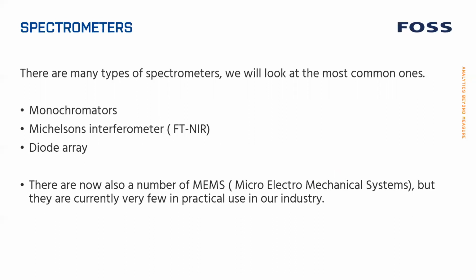How deep will NIR light penetrate into the sample in reflectance mode? Suppose sample are well grind. Well, if you do reflectance, in the shorter wavelength range, it will penetrate maybe 1 to 2 millimeters. When you go higher up around 2000, it will be maybe 0.1, 0.2 millimeters. So it's a very narrow part of the surface it will penetrate. And you can compare that then to an Infratec where you have normally 18 millimeter for a wheat sample or a meat sample where you have 13 millimeters. So when you use the lower wavelength range, you get a much bigger representation of the sample.